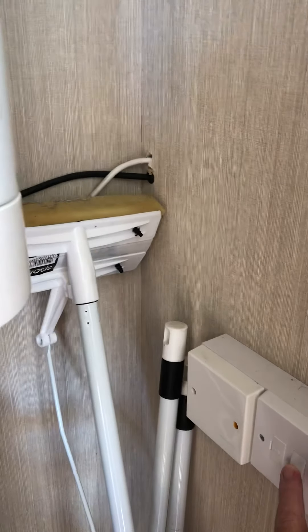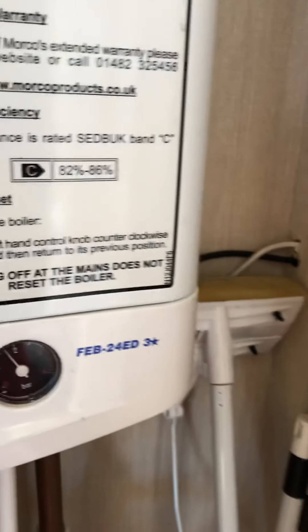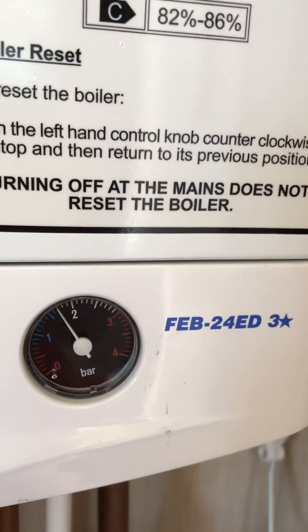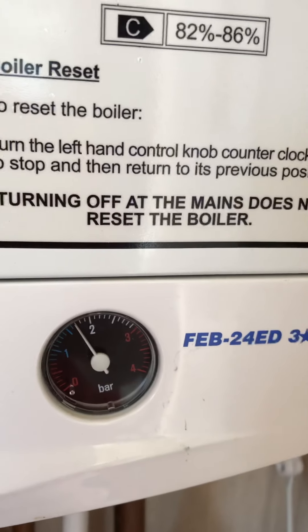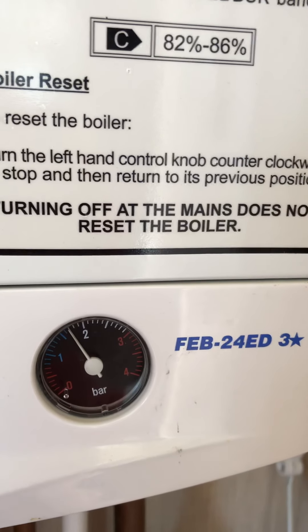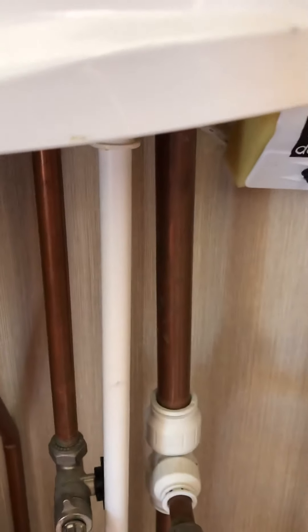...to do on the right hand side is the electric switch which powers the boiler, so make sure that's switched on. Then you need to check the pressure gauge — at the moment this is showing just over one and a half, so that should be enough for the boiler to fire up. If it's less than one, it certainly won't fire up.